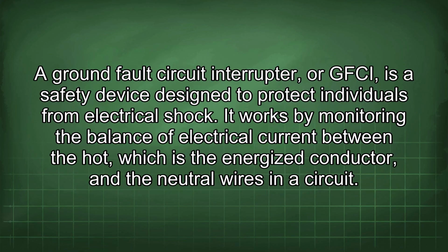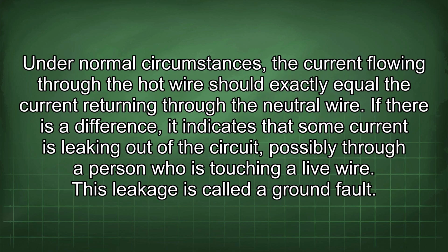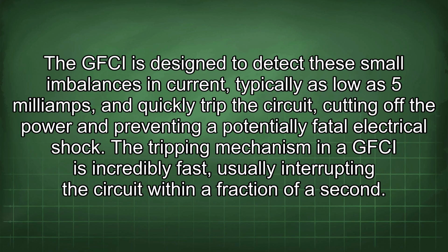A ground fault circuit interrupter, or GFCI, is a safety device designed to protect individuals from electrical shock. It works by monitoring the balance of electrical current between the hot, which is the energized conductor, and the neutral wires in the circuit. Under normal circumstances, the current flowing through the hot wire should exactly equal the current returning through the neutral wire. If there is a difference, it indicates that some current is leaking out of the circuit, possibly through a person who is touching a live wire. This leakage is called a ground fault. The GFCI is designed to detect these small imbalances in current, typically as low as 5 mA, and quickly trip the circuit, cutting off the power and preventing a potentially fatal electrical shock.